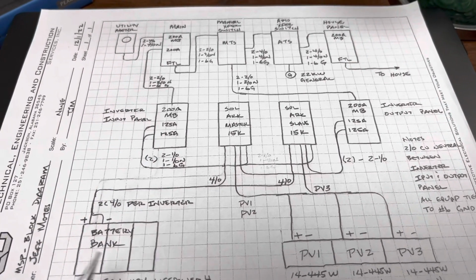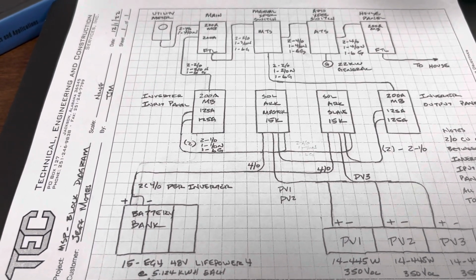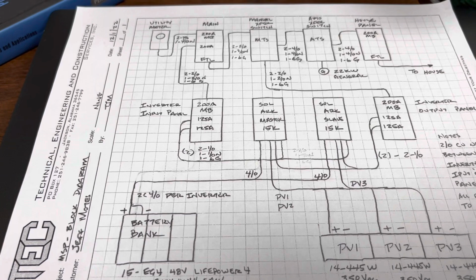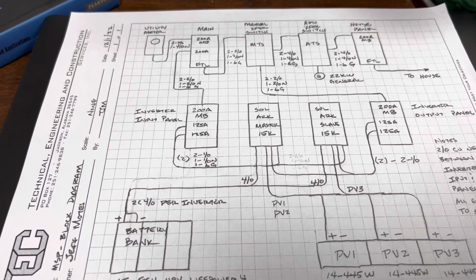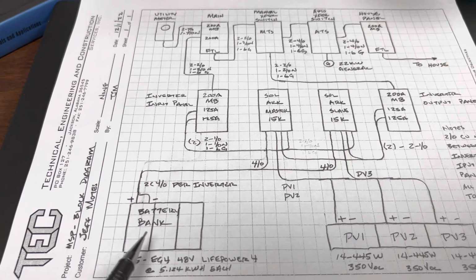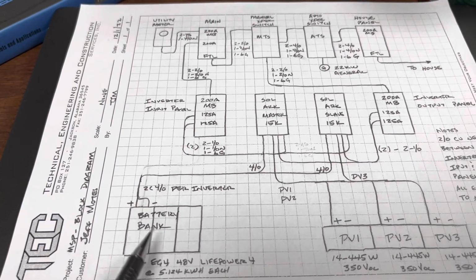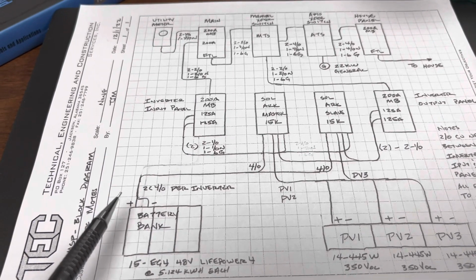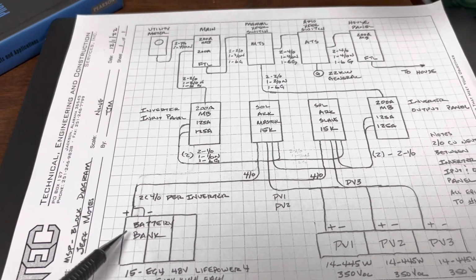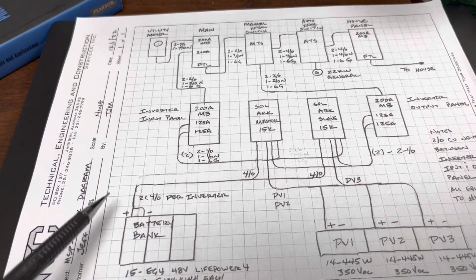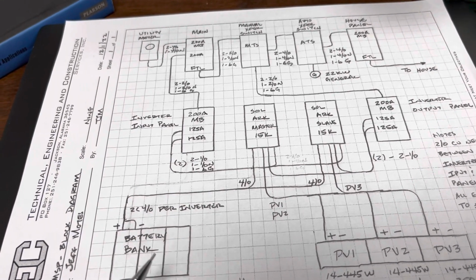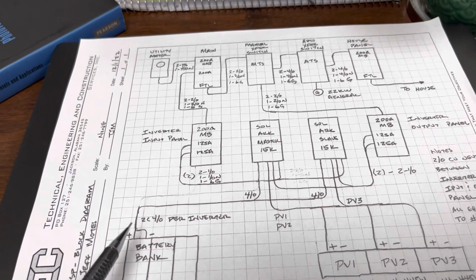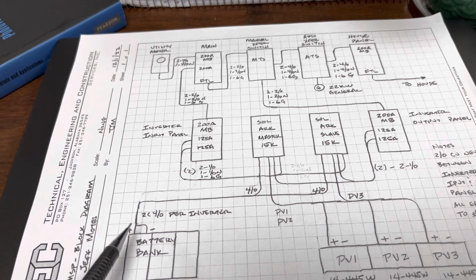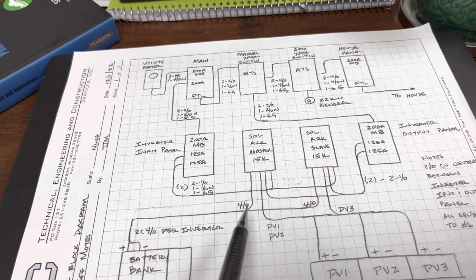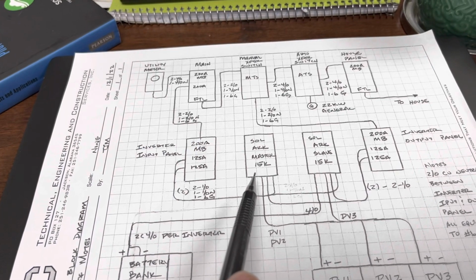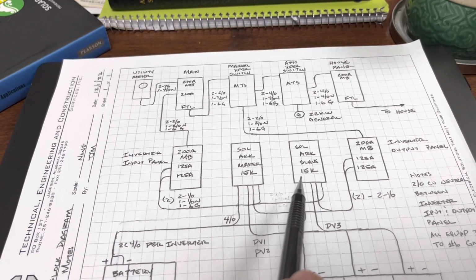So I charge the battery, and this is 15 EG4 48 volt 5.12 kilowatt hour batteries. I bought these from Signature Solar. They're working good. Anyway, there's 15 of them, and they're bussed, and I have a 4-aught copper run from the battery bank for each Sol-ark. So there's 2 4-aught copper runs from the battery bank back over to my inverters. 1 set, positive and negative, goes to the master. 1 positive and negative goes to the slave.